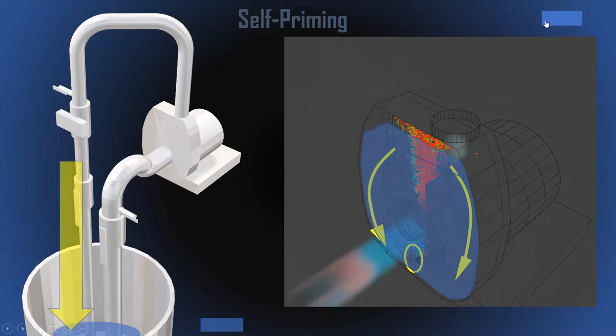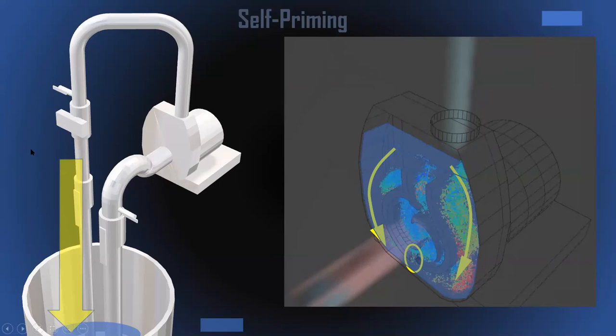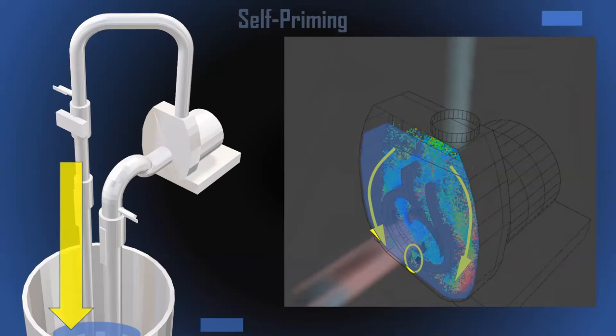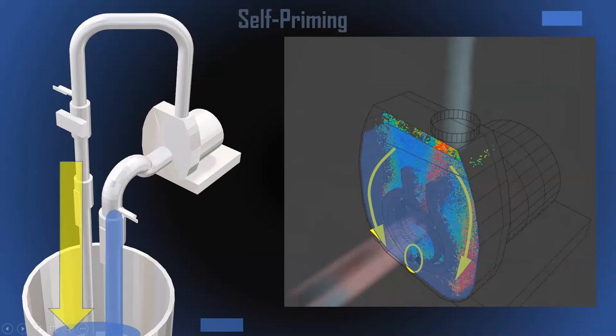By reusing this liquid over and over, we generate a vacuum in the eye of the impeller. On the suction side, atmospheric pressure — shown by the yellow arrow — is pushing down on the surface of the fluid in the tank. This creates a differential: low pressure in the middle of the impeller, higher pressure outside on the fluid. Fluid is therefore pushed up the pipe — the pump isn't sucking; the impeller generates a low-pressure zone and atmospheric pressure pushes fluid toward it.